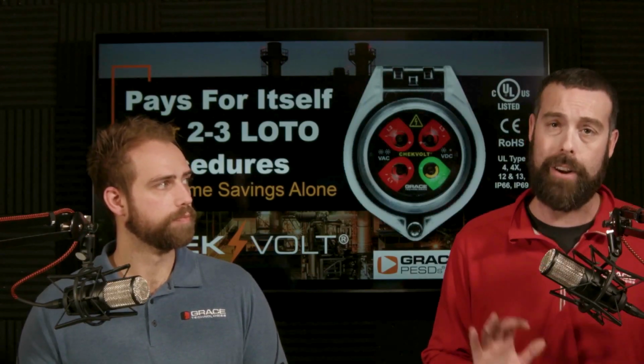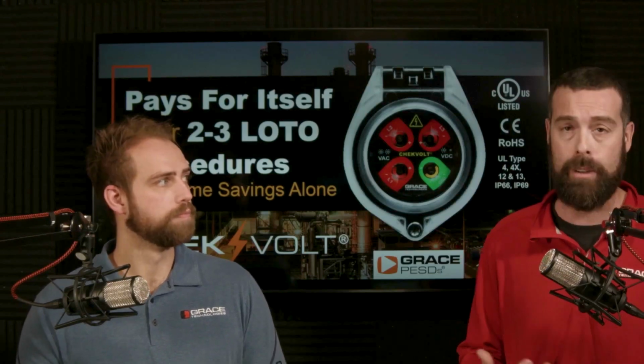Yeah, and that's like performing a contact test with an adequately rated portable test instrument. In essence, I don't want to get too sidetracked, but we call this a live-dead-live test. In essence, what that means is you're testing your meter on a known voltage source to ensure that it's field calibrated and working as it should. We also add redundancy into this process. We recommend testing live through the actual permanent electrical safety device, doing your absence of voltage and presence of voltage verification testing, phase to phase, phase to ground, then locking out or disconnecting your isolator switch, testing it dead at the actual device through the permanent electrical safety device, and then again testing your meter on a known voltage source to wrap it up.